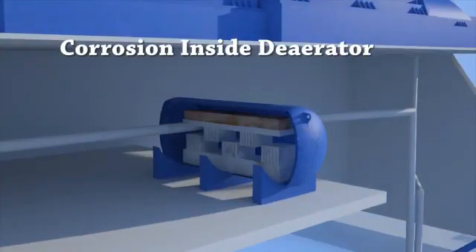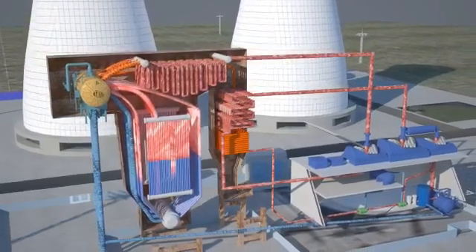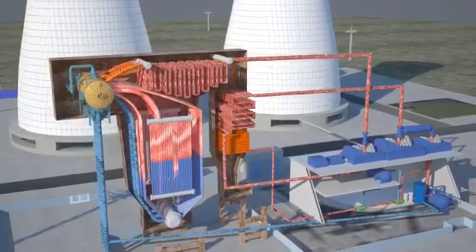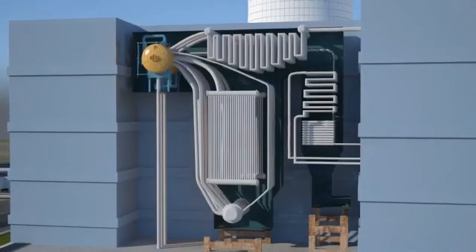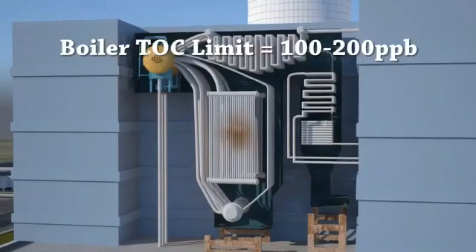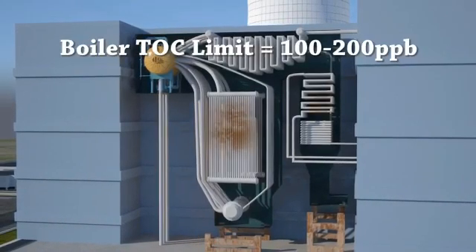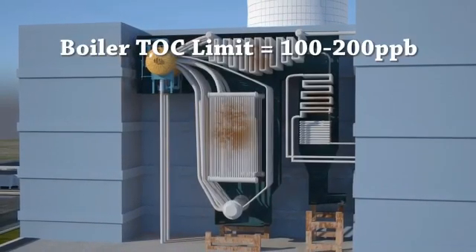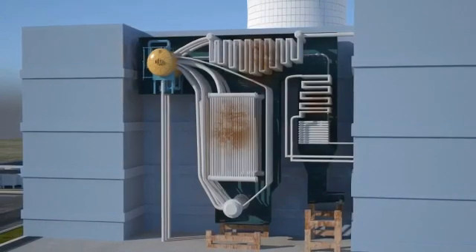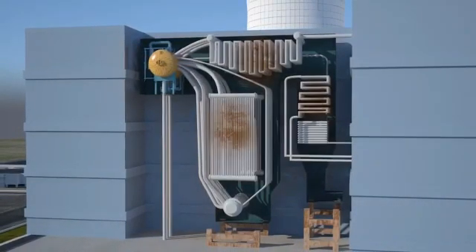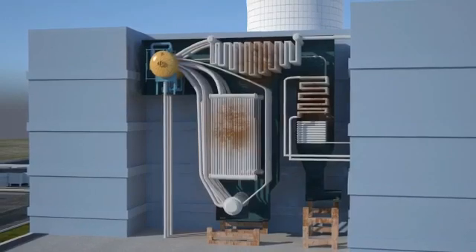Deaerators, which are crucial. This decreases performance and can even cause a breakdown of the entire boiler turbine system. Thus, it is regulatory to maintain the TOC levels. The TOC limit for boiler water is 100 to 200 parts per billion.